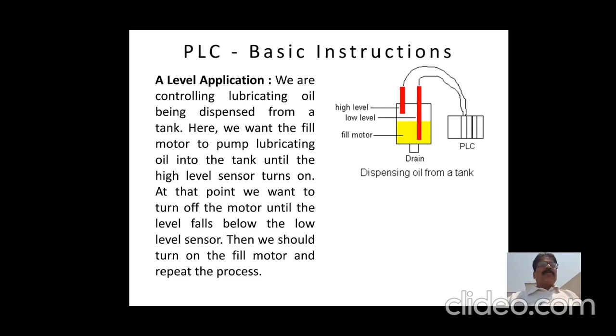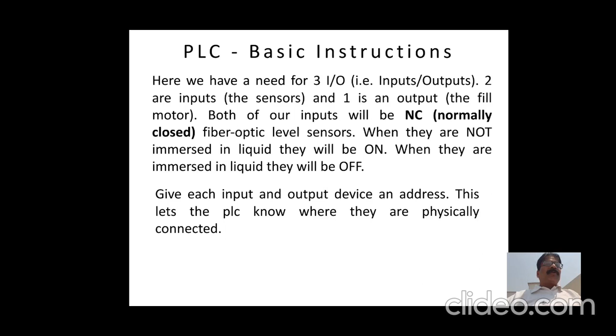Here we have three IOs, inputs and outputs. Two are inputs, that is the sensors, and one is the output, that is the fill motor. Both of our inputs will be normally closed. We can use fiber optic level sensors. When they are not immersed in liquid, they will be on. When they are immersed in liquid, they will be off. Give each input and output device an address. It is shown in the next diagram.